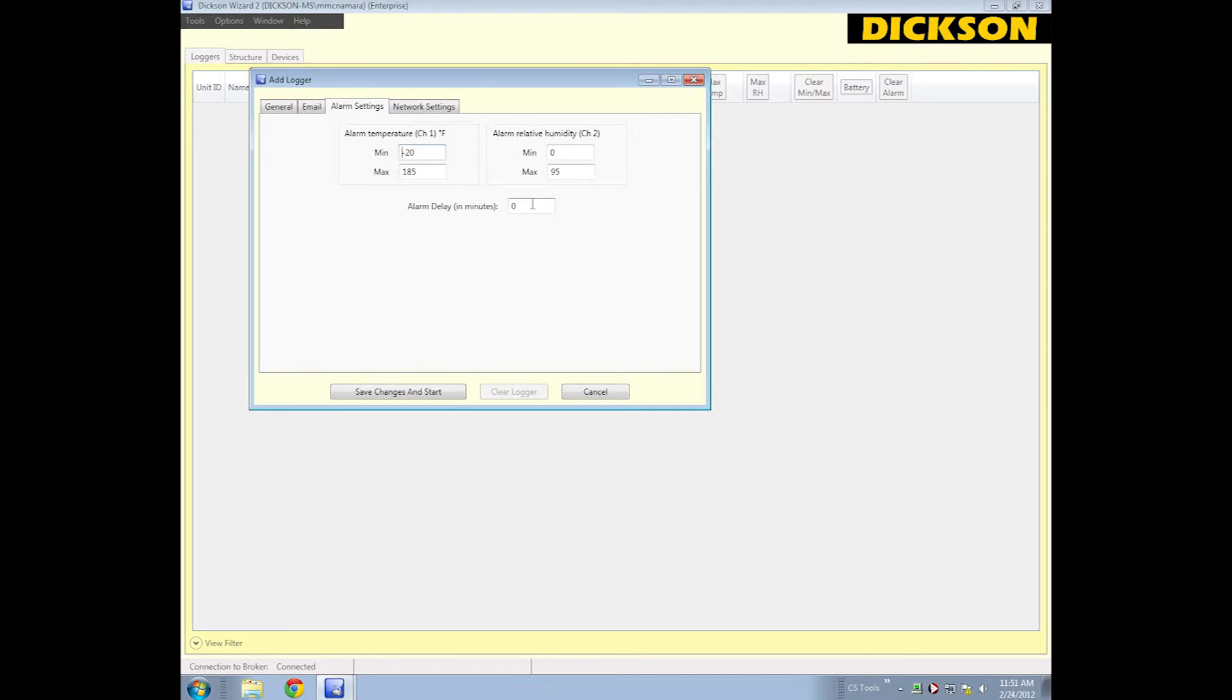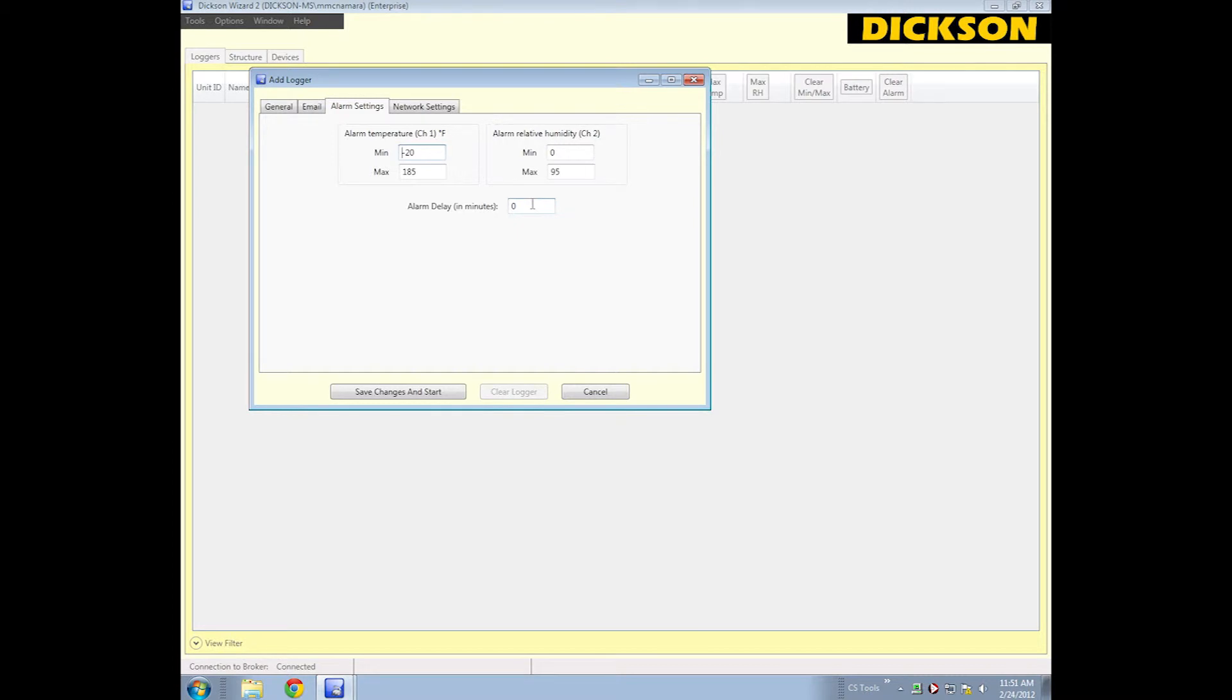You can also set the alarm delay, which allows you to say if it hits this condition, I want you to wait two minutes, five minutes, ten minutes, or whatever your protocol says to wait to inform me that there's an issue occurring. Something like opening a refrigerator door will cause a burst of warm air, and then the logger may go off.